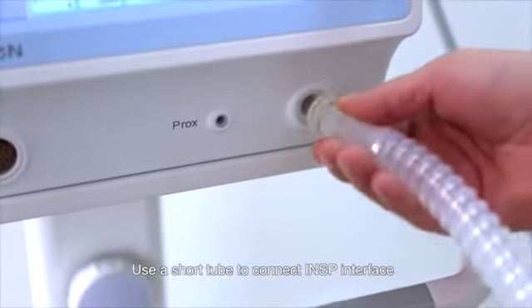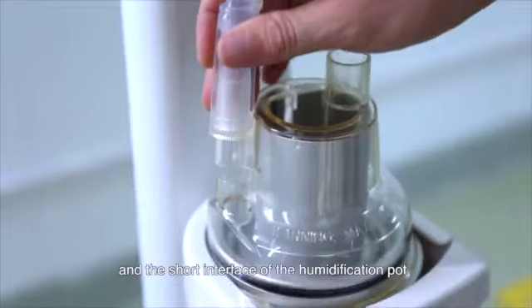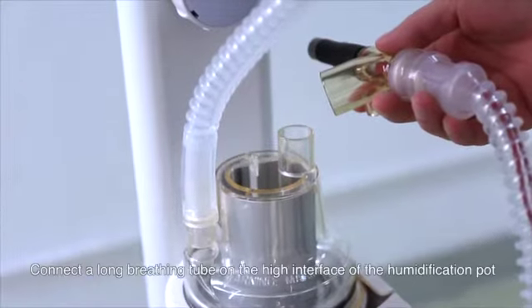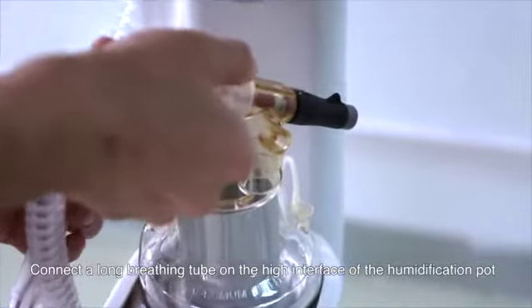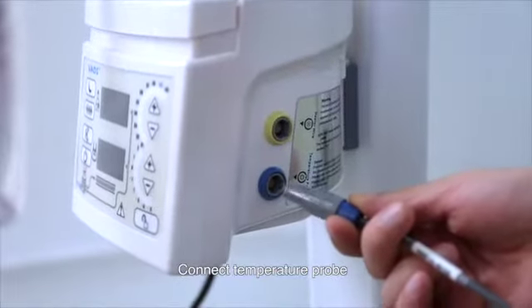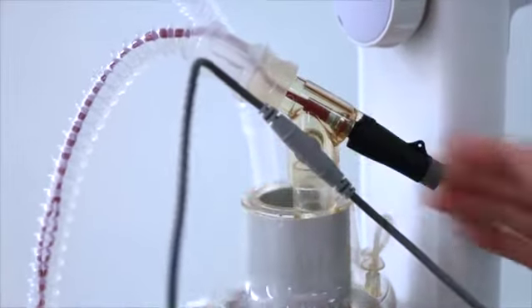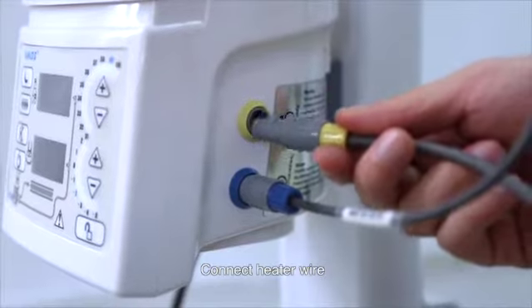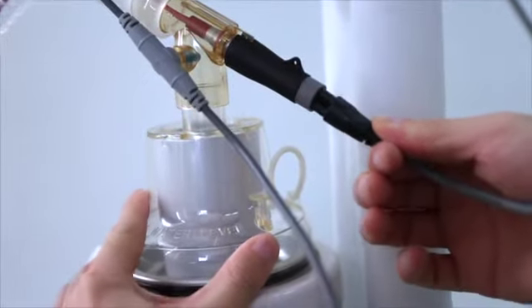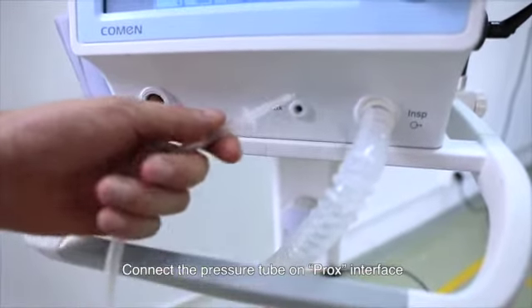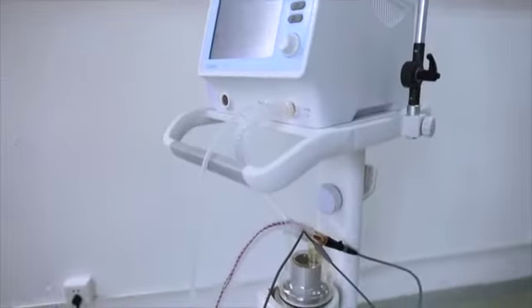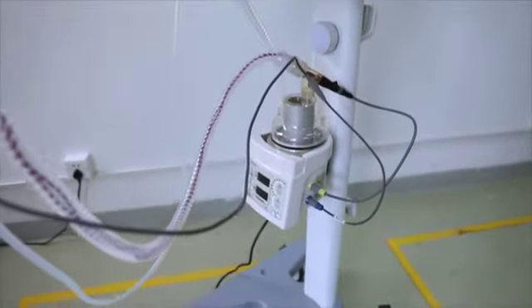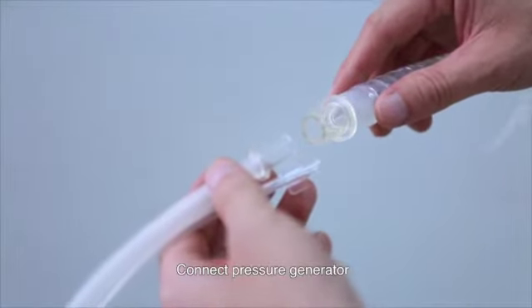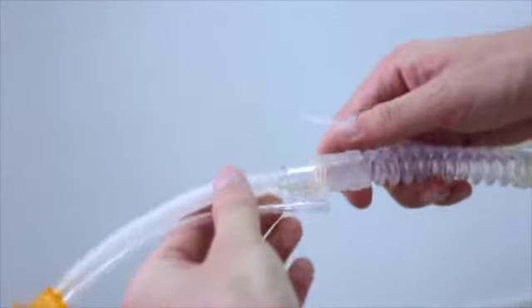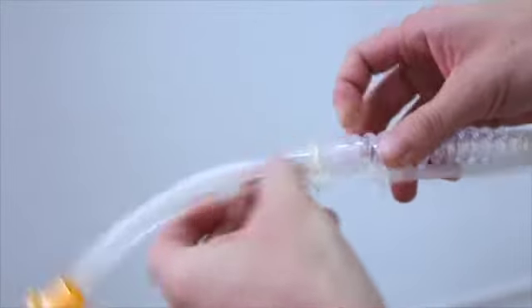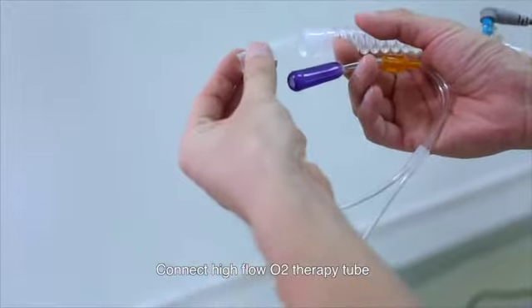Use a short tube to connect the INSP interface and the short interface of the humidification pot. Connect a long breathing tube on the high interface of the humidification pot. Connect the temperature probe. Connect the heater wire. Connect the pressure tube on the prox interface. Connect the pressure generator. Connect the high-flow oxygen therapy tube.